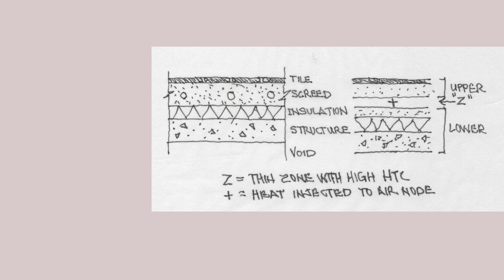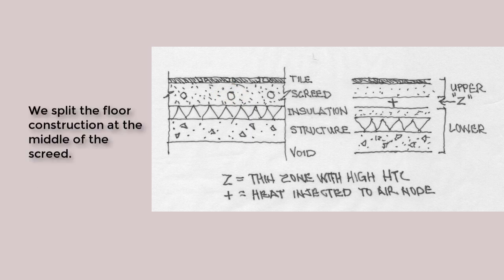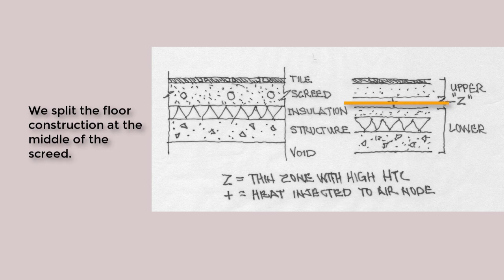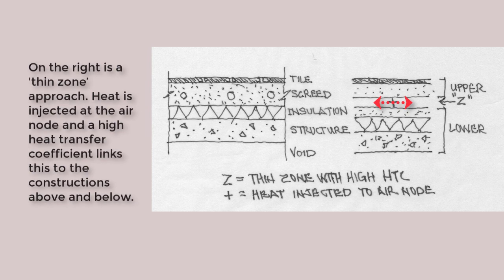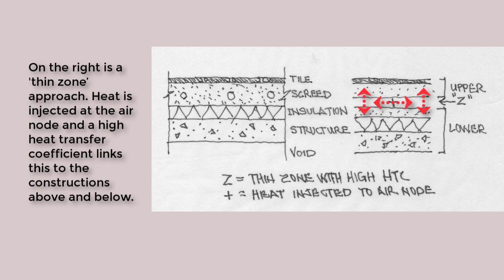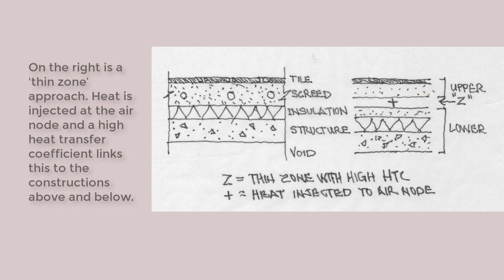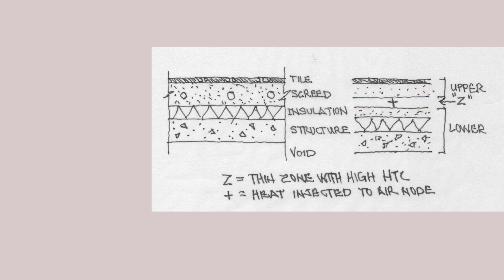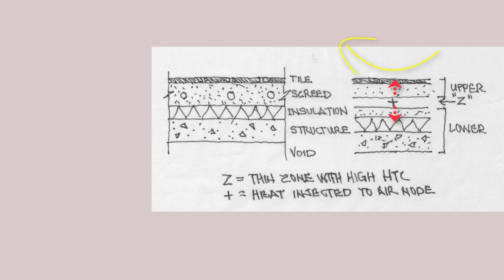In this video, we will explore a thin zone approach to floor heating. We'll split the composition of the floor structure, the middle of the screed, and substitute the heating element with a thin body of air. We will set a high surface heat transfer coefficient so that any heat injected into the air gets transferred into the floor structure. The thin zone approach ends up using 1D conduction but does so in partnership with the dynamic responses of conduction and surface heat transfer regimes available within the simulation.